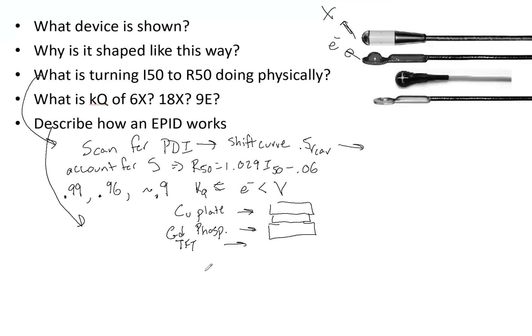So amorphous silicon takes, ultimately, there are a couple types. What we mainly now is this, you know, amorphous silicon. And it takes the x-ray, I probably didn't need to write takes, but it takes the x-ray photons to light, photons to charge. And then that is integrated and can give you, ultimately, whether it's your fluence or your MV images, wherever it may be. So that's kind of a very brief overview of how EPID works.